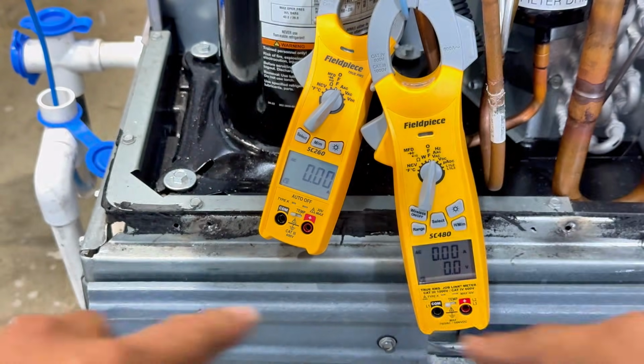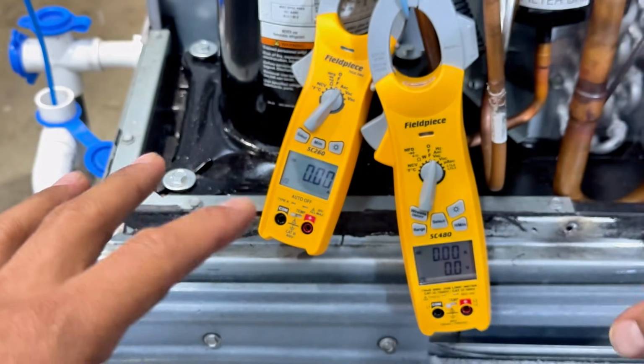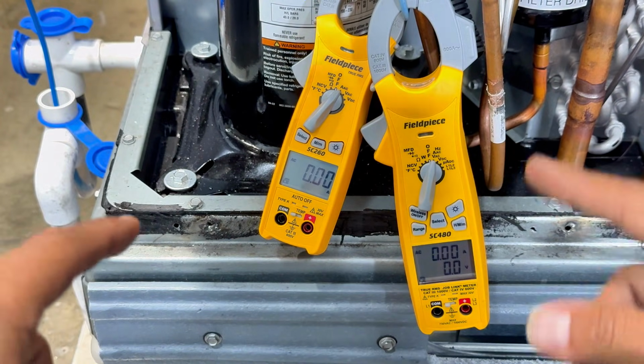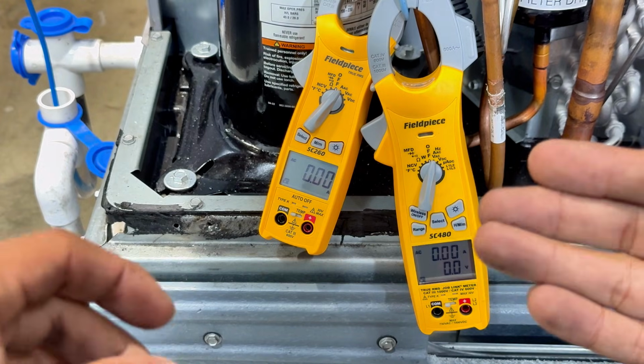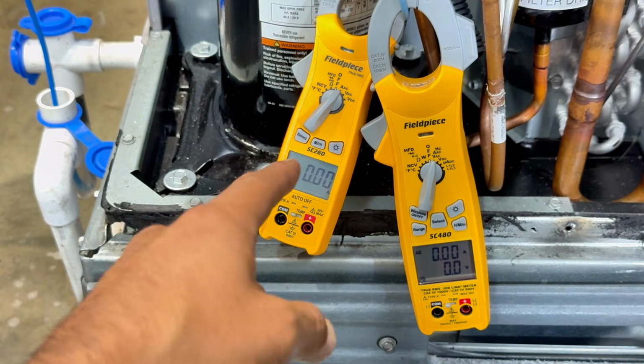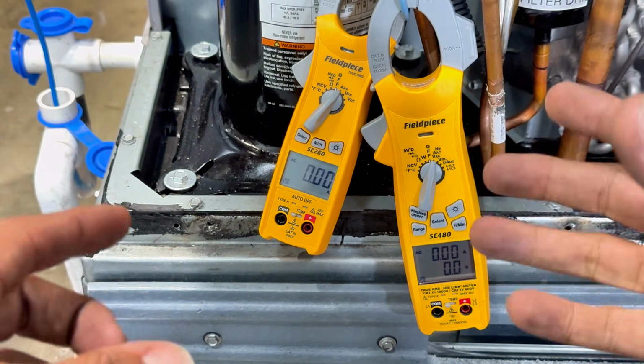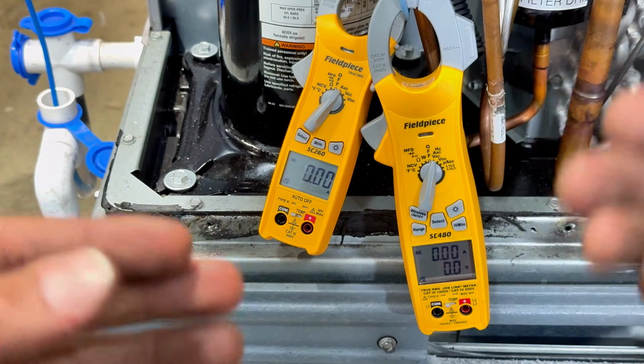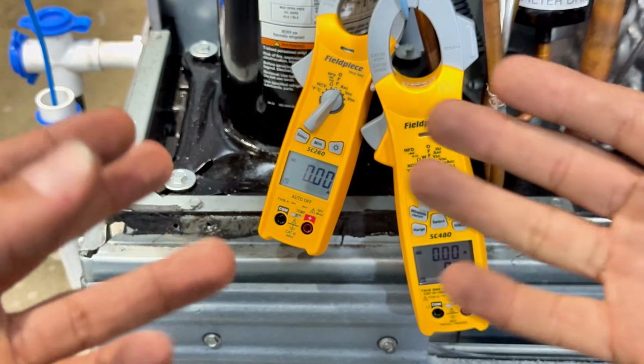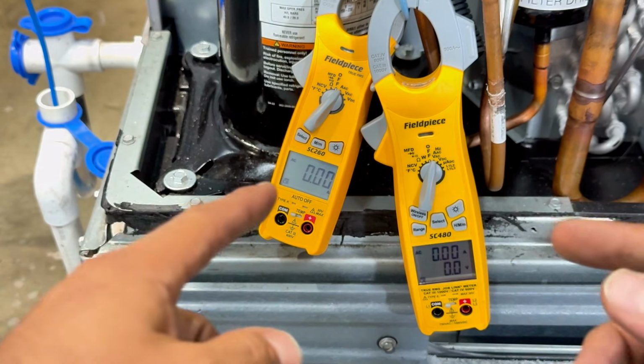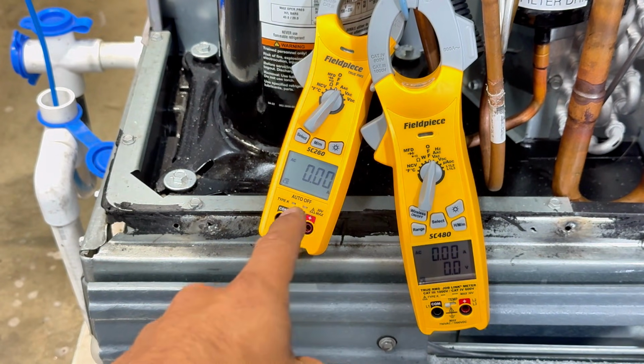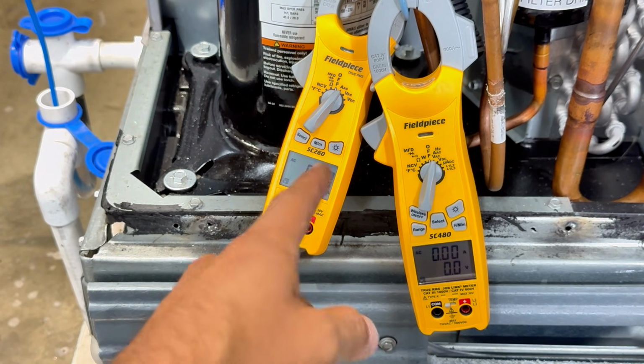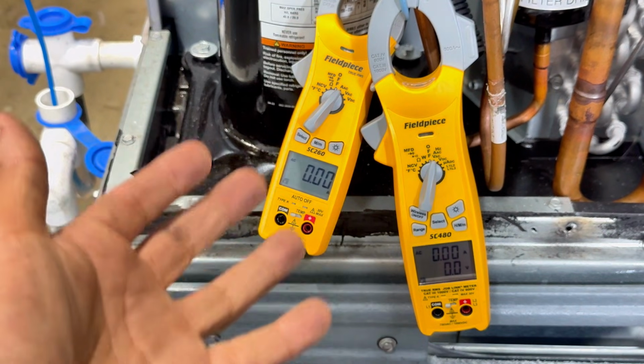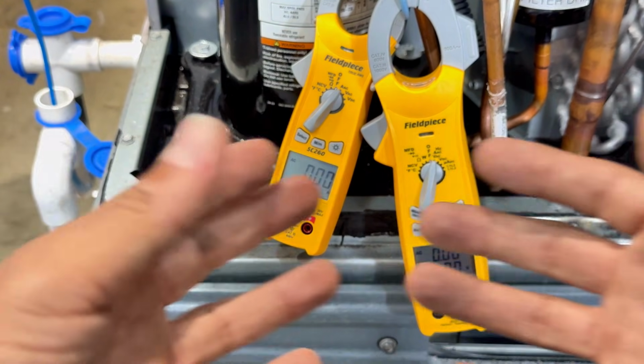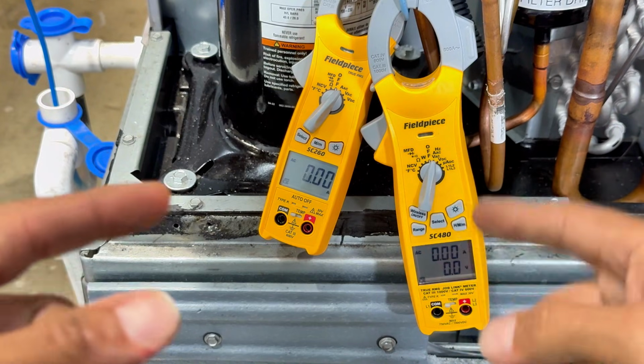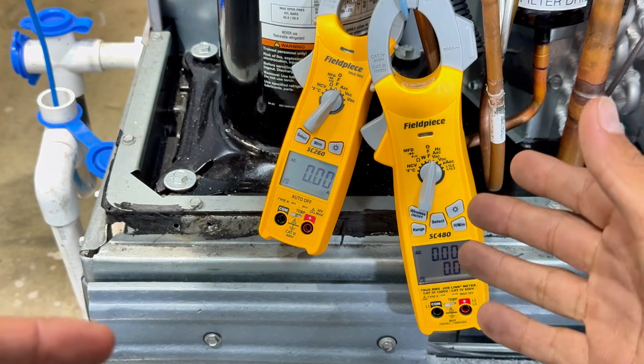The engineers are already in the lab somewhere, and they already said that when that capacitor is weak or doesn't have a good microfarad reading, the most this compressor is going to pull is the locked rotor amps they put on the plate, which is 59.5. But right now, as you were able to see, it pulled close to 53, 54, and that's pretty high. That current doesn't know what to do, because the start winding had no capacitor.